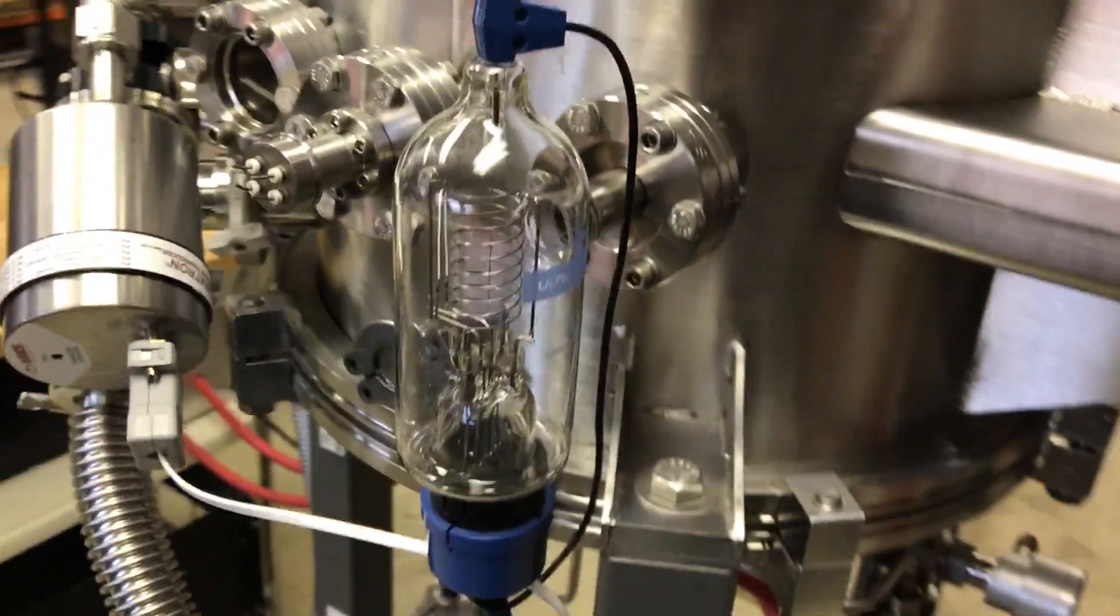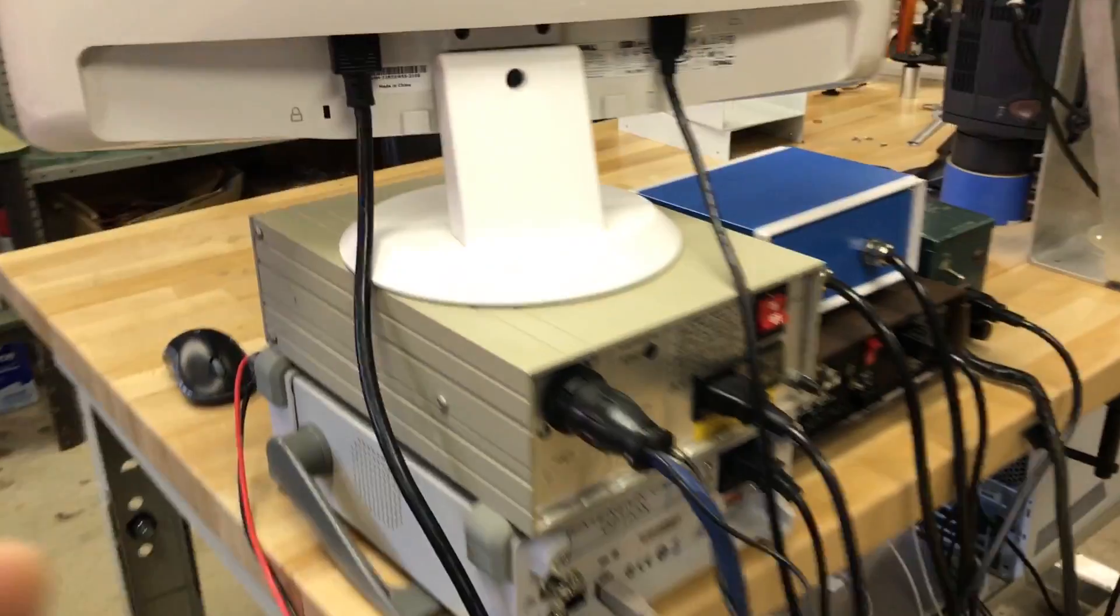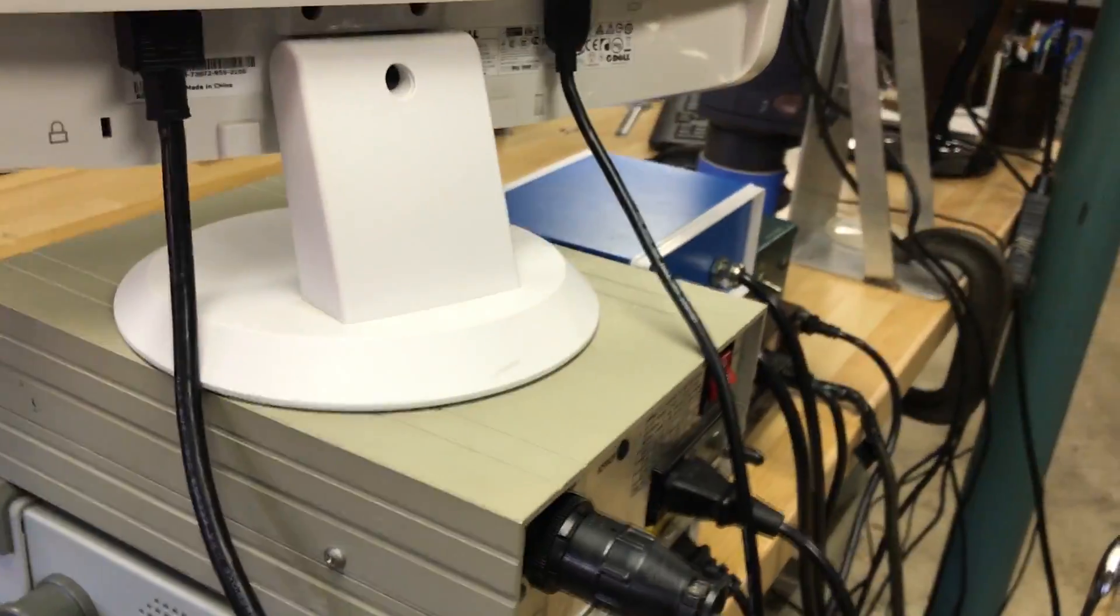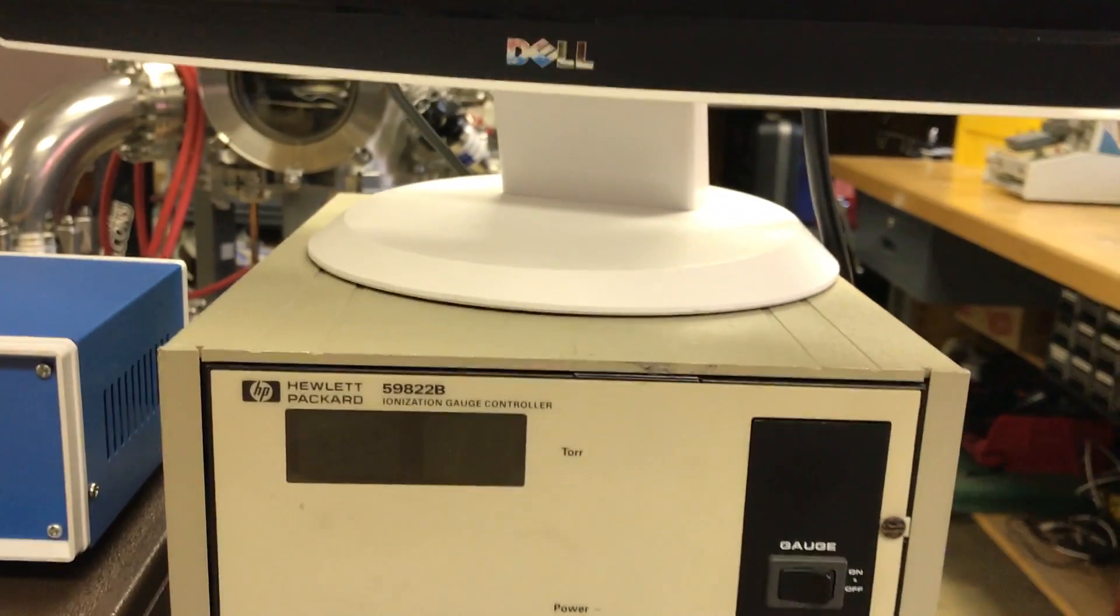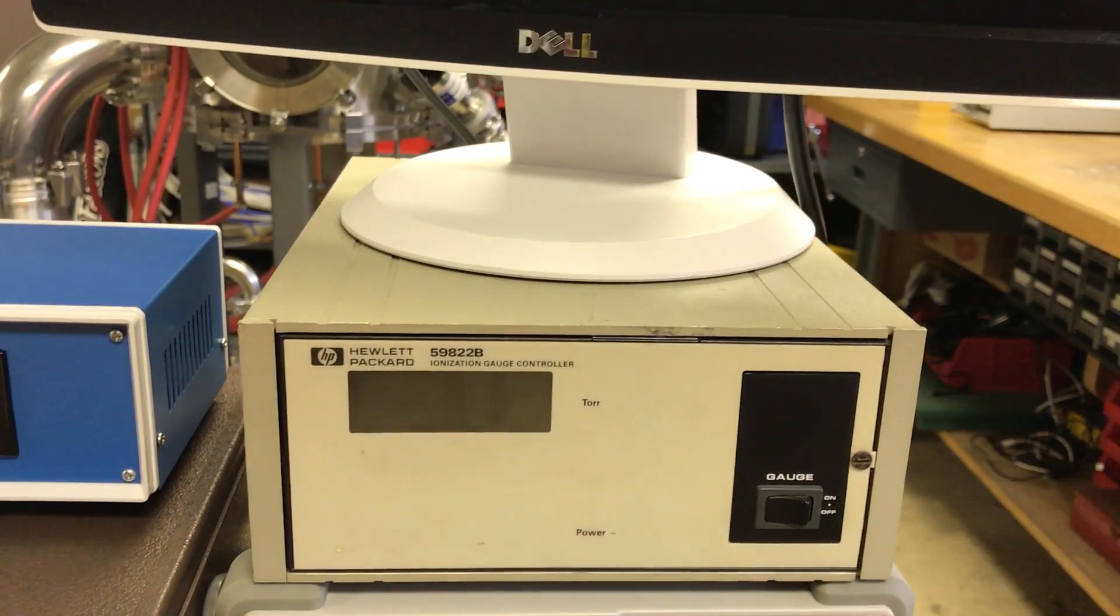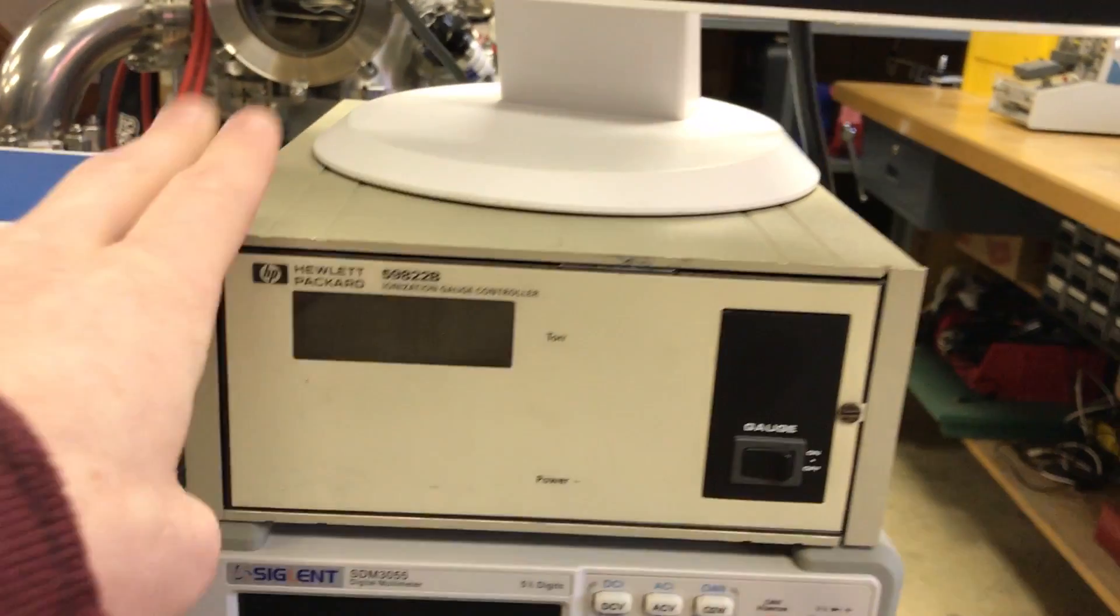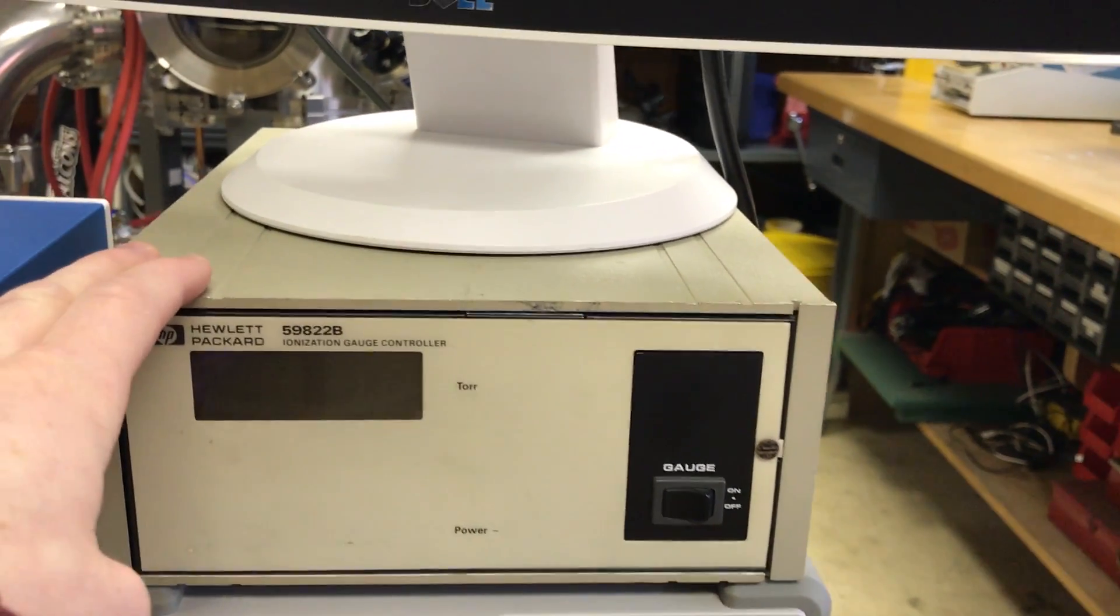And then that blue cable runs all the way over here to the HP ionization gauge controller, and that's right here. I can't turn this on until basically when I turn the turbo pump on. This can come on, otherwise the filament will burn out.